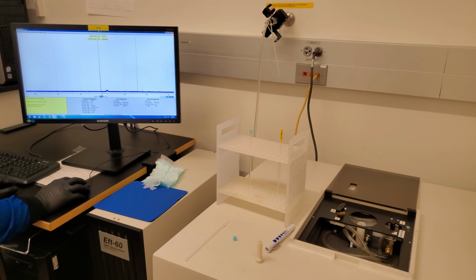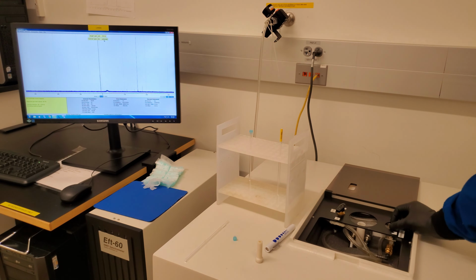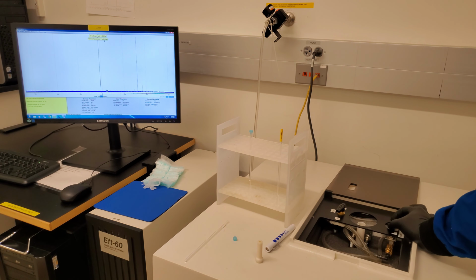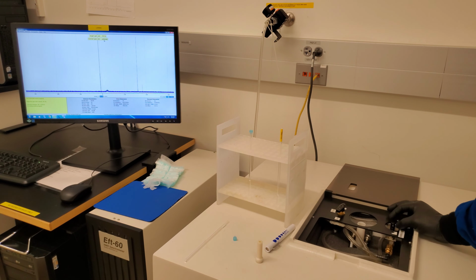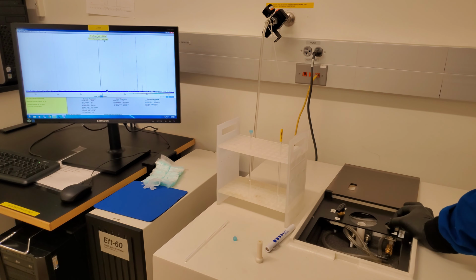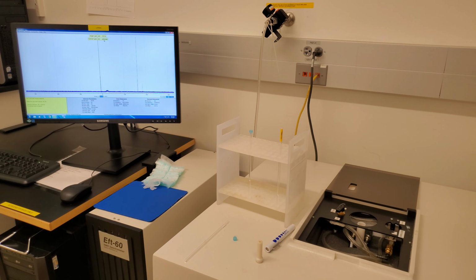Up at the top it tells you the target spin rate, 39 Hertz, and the current spin rate. Currently the air is not working, so the spin rate says unknown, but it should tell you the current spin rate. You can adjust the spin rate with the knob on the right side of the magnet. Clockwise decreases it, counterclockwise increases the spin rate. You want to slowly adjust this knob until the current spin rate matches the target spin rate.